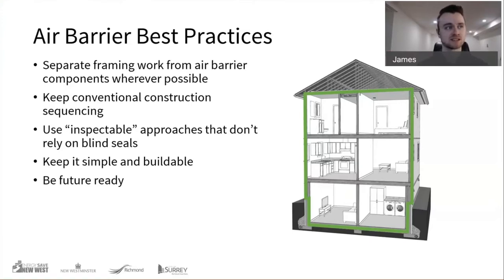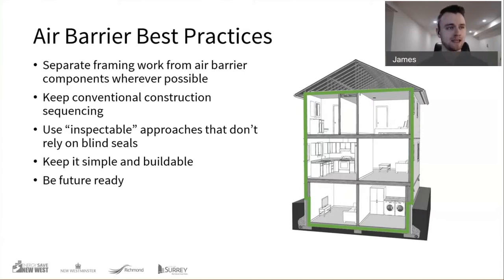Third: relying on reviewable, inspectable airtight approaches — tapes and seals that we can see, not blind seals placed behind large components that can never be viewed again. That's unreliable. Fourth: being future-ready. The concept is getting to a point where we know we can hit air tightness targets and are ready for increased targets — simple and buildable, maybe some mockups — without having to reinvent our air tightness approach every time the code minimum advances to the next step.